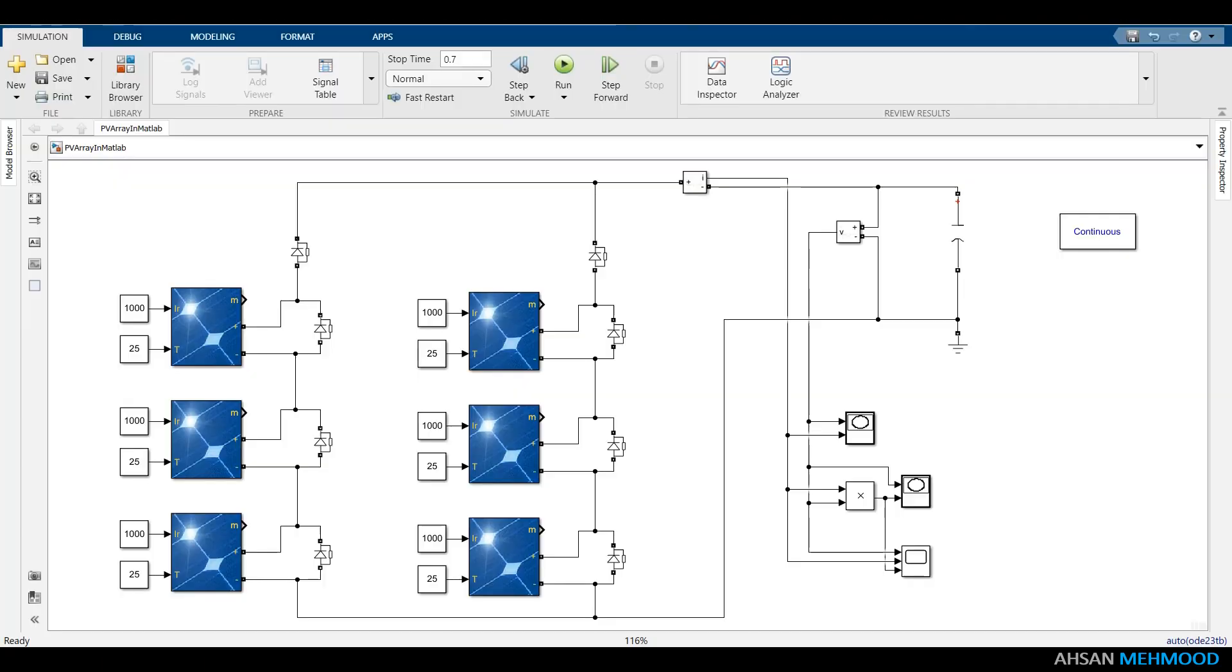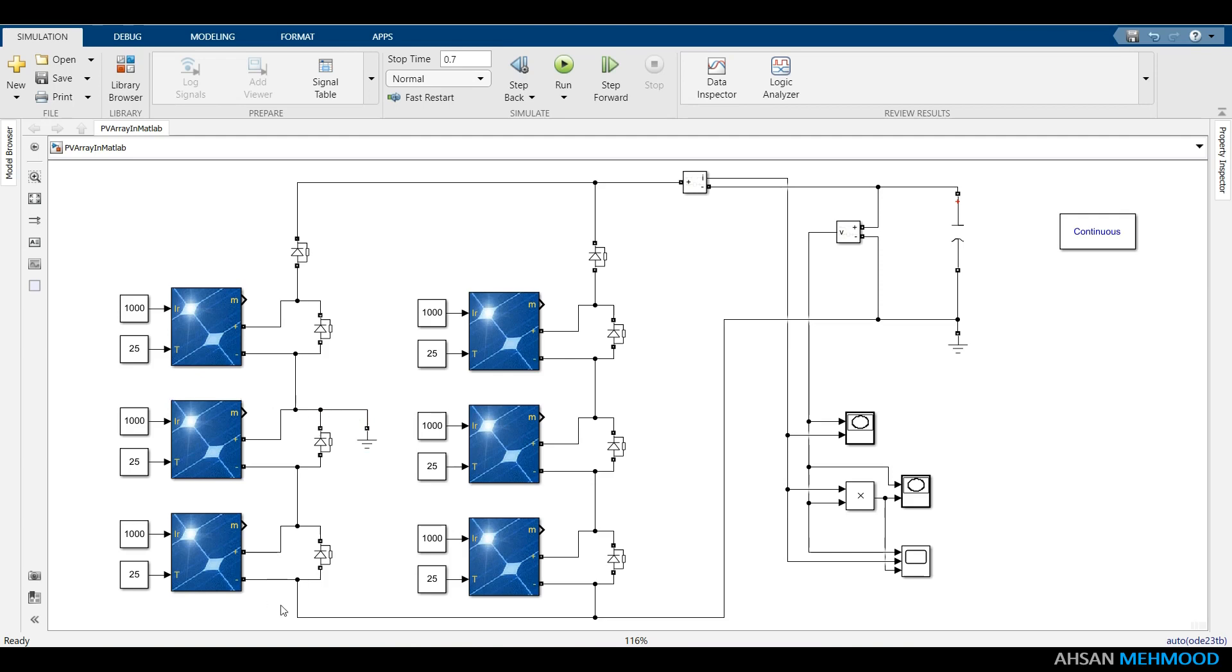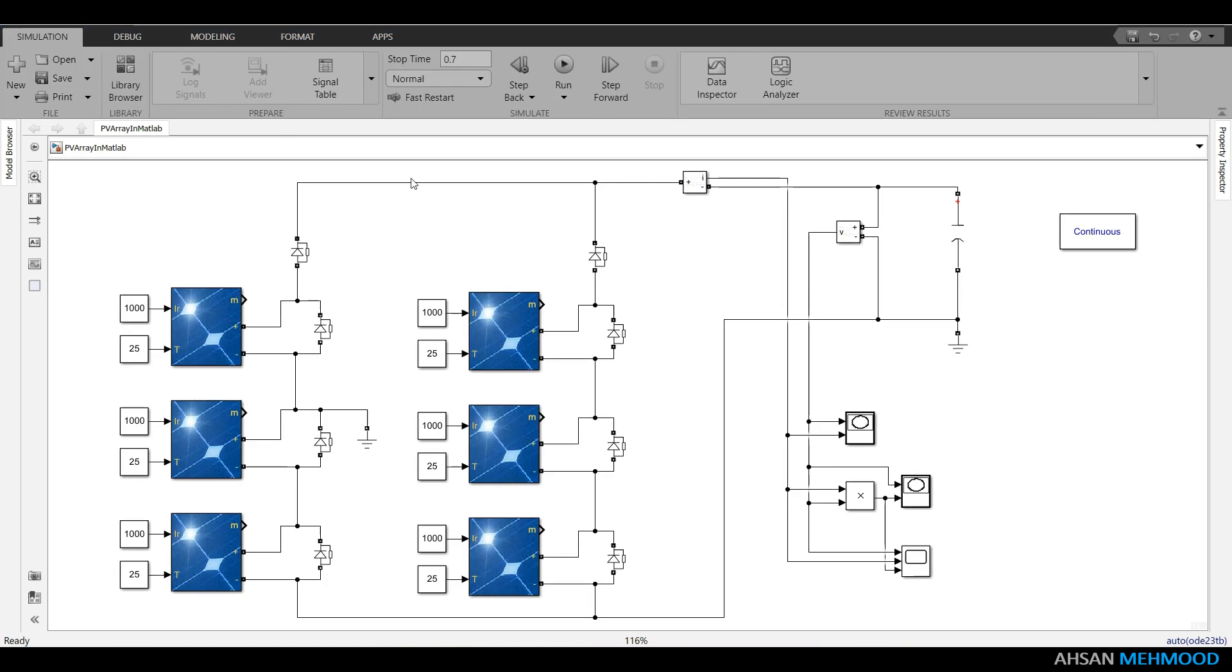I will give you the demonstration of line-to-ground fault and line-to-line fault between strings. For this purpose, set irradiation values back to 1000W per meter square. To induce line-to-ground fault in string 1 with 67% mismatch, connect the positive terminal of the second module to the ground. Which means lowest two modules of string 1 are short-circuited and only top module of string 1 is healthy or functioning properly throughout the entire voltage range.